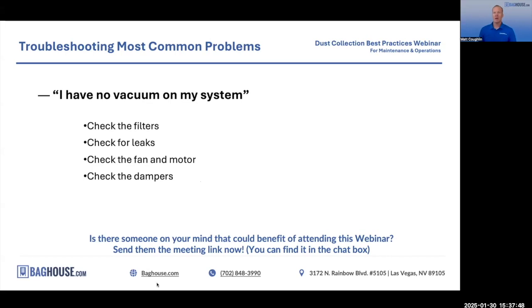And how do we do that? We go look at the differential pressure gauge on the baghouse. So every collector should have a DP gauge or a magnehelic gauge or a differential pressure gauge, all the same thing, right? It'll just tell you what that static or differential pressure is across your filter. So brand new set of filters, maybe at 1 or below 1 inch water is the unit most often used. As the filters get packed with dust, that will creep up to 2, 3, 4, 5 inches. And at some point, your filter cleaning system will kick on, blast it with compressed air or shake it, depending on your system. Whatever it is, it should knock the dust off. Static pressure goes down. And it should basically go back to operating the way you want.